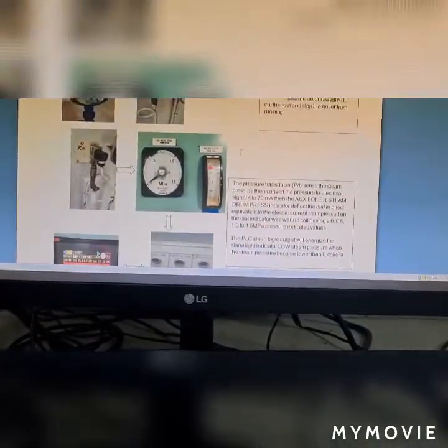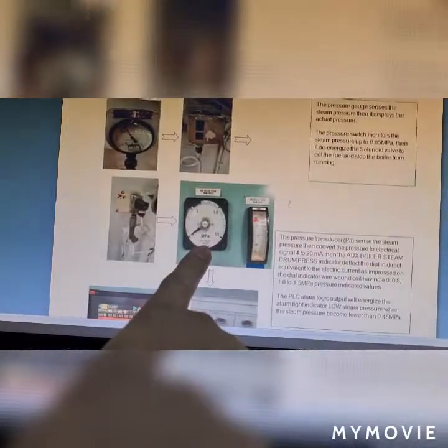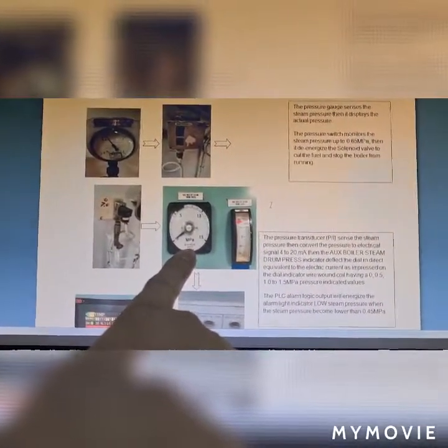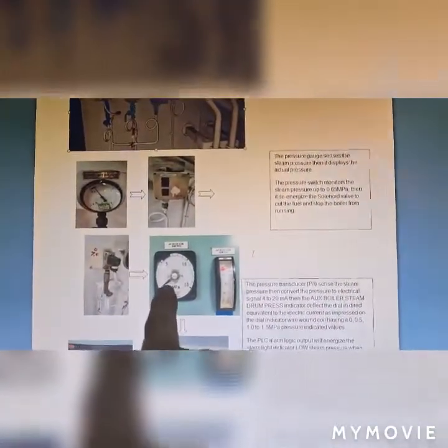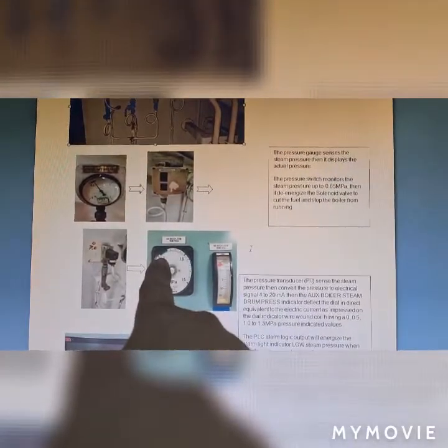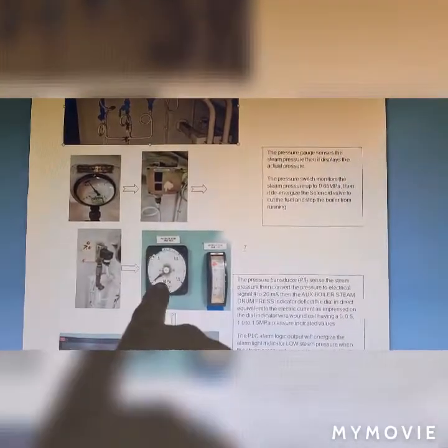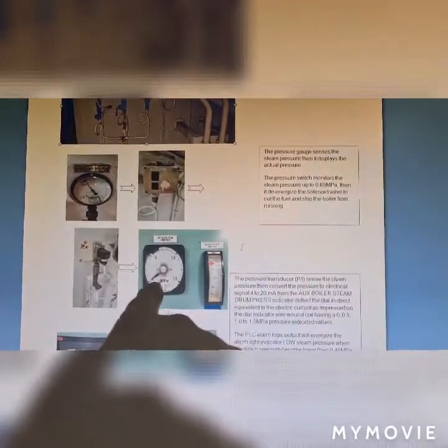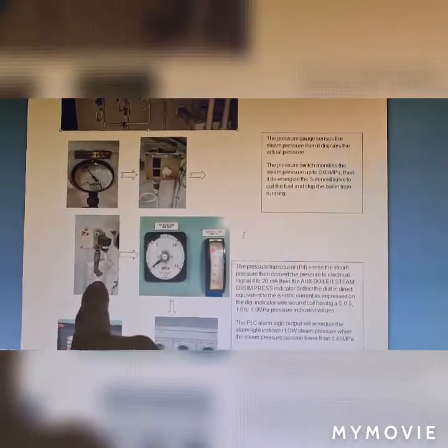Down here, you will find what you call the pressure transmitter, the steam pressure indication as what you have seen in the engine control room. Take note, while the boiler is running, the steam pressure increases from 0.1, 0.2, 0.3, and 0.5 to 0.7. The steam pressure displayed here is the equivalent of the P2I, meaning pressure to current signal converter, from this instrument, that is a pressure transmitter.